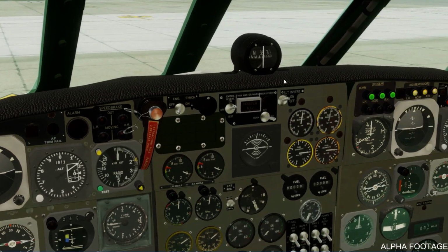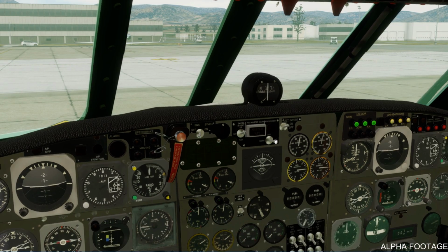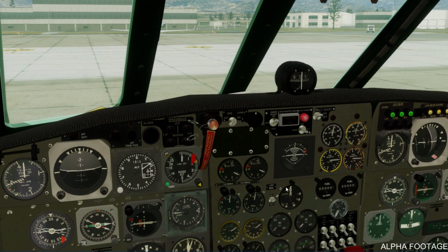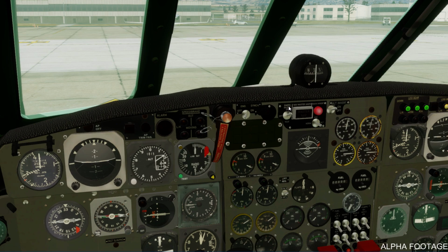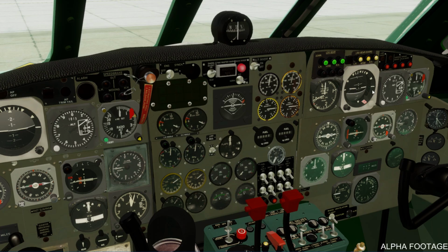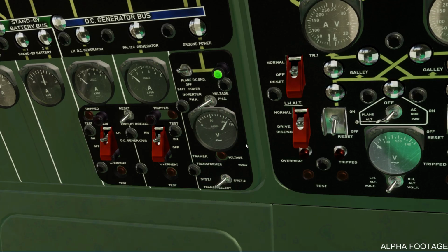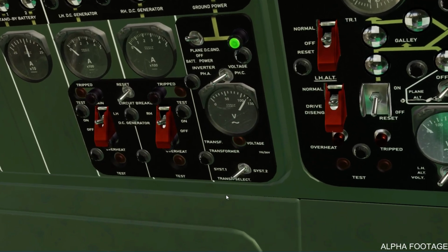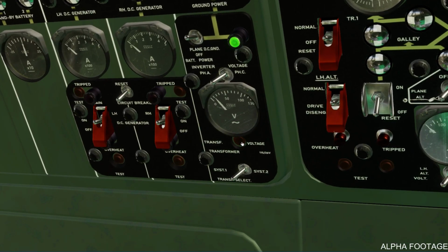Set the main inverters to the position off. You can see now the emergency inverter has kicked in, so the captain's instruments are powered and the co-pilot instruments are not. Check that the red warning light comes on. Checked. Voltage is approximately 115 volts. And now we also check the transformer voltage should be 0, and this is to make sure the current we see here comes from the emergency inverter.